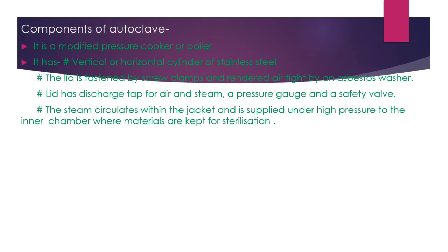Components of the autoclave: it is a modified pressure cooker or boiler consisting of a vertical or horizontal cylinder made of stainless steel. The lid is fastened by screw clamps and rendered airtight by an asbestos washer. The lid has a discharge tap for air and steam, a pressure gauge, and a safety valve. Steam circulates within the jacket and is supplied under high pressure to the inner chamber where materials are kept for sterilization.